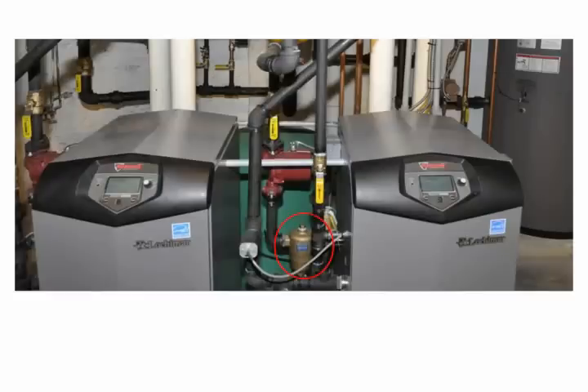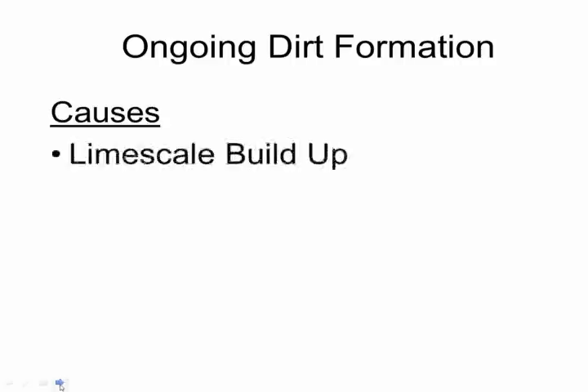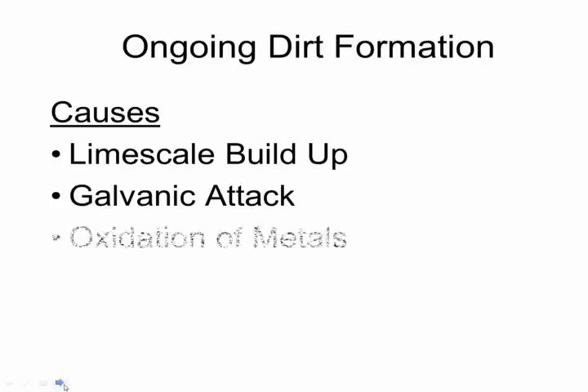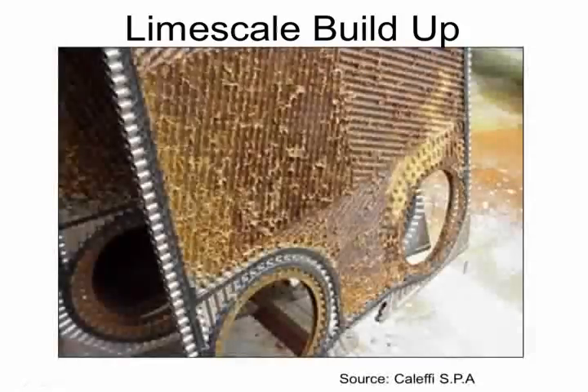Sometimes it could get hung up in the system, and devices such as, in this slide, dedicated dirt separation devices come into play to protect the very efficient heat exchanger perhaps on that boiler. We'll come back to these dirt separators. But the bigger issue as it relates to dirt is when the system's up and running, everyone's paid, and they walk away from the job, and the system's going. So what happens on an ongoing basis? Well, dirt can form by limescale buildup, which is one form of what's basically called dirt. It shouldn't be there. Galvanic attack, and the classic case of rusting or oxidation of metals. We're going to take a look at each of these one at a time, about what causes them and how to steer around them. So starting off with limescale as an example.